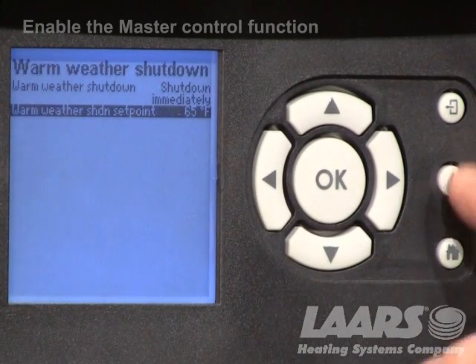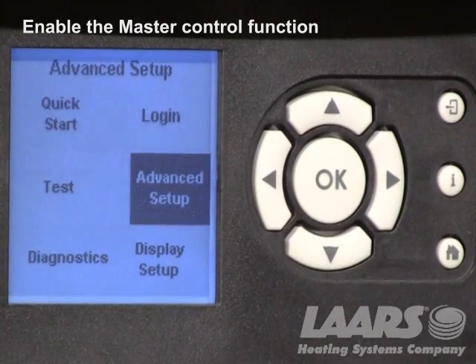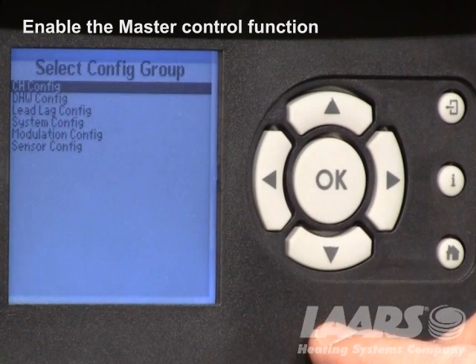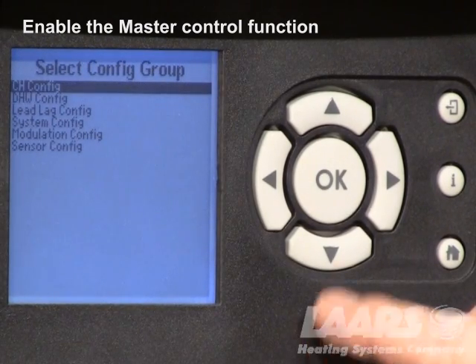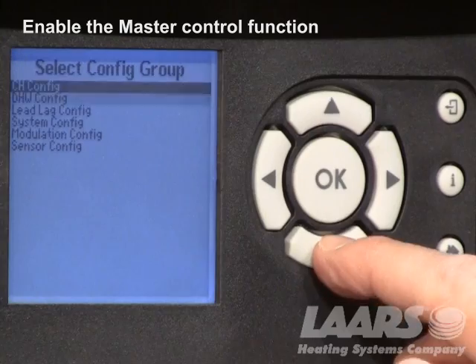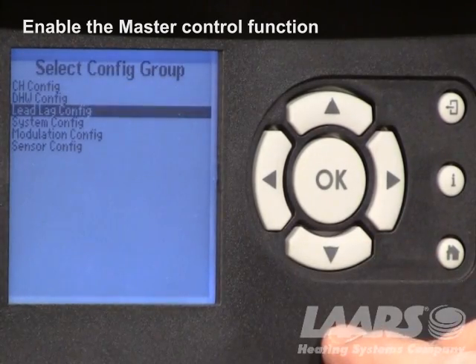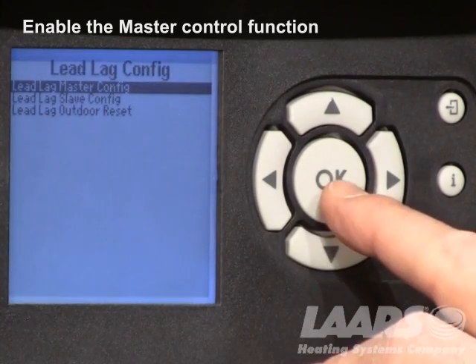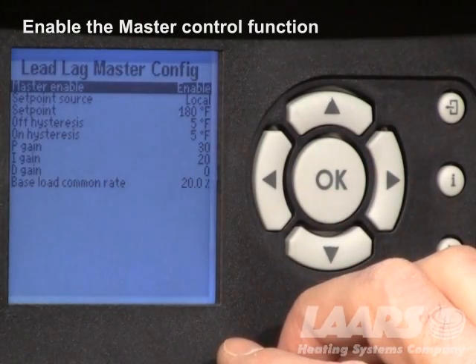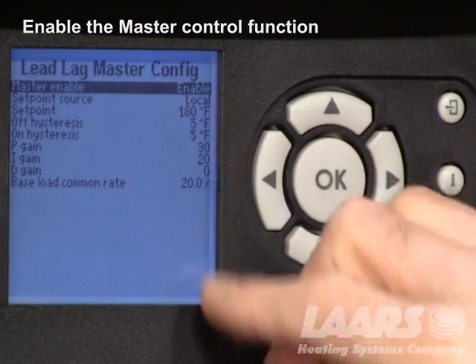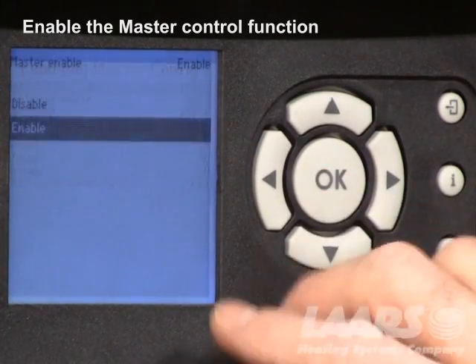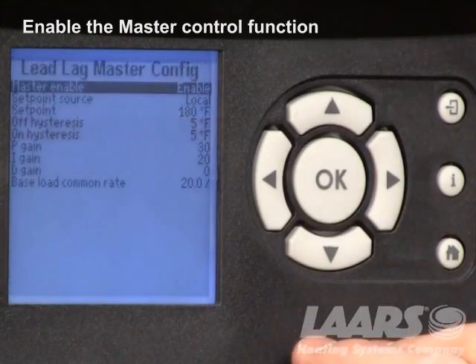Next, go back to advanced settings and enable the master control. Choose advanced settings, go down to lead lag configuration, highlight lead lag configuration, press okay, and here's the lead lag master control. This should be enabled — go in and check it. If it's disabled because someone was adjusting the control, highlight enable and choose enable, then press okay.